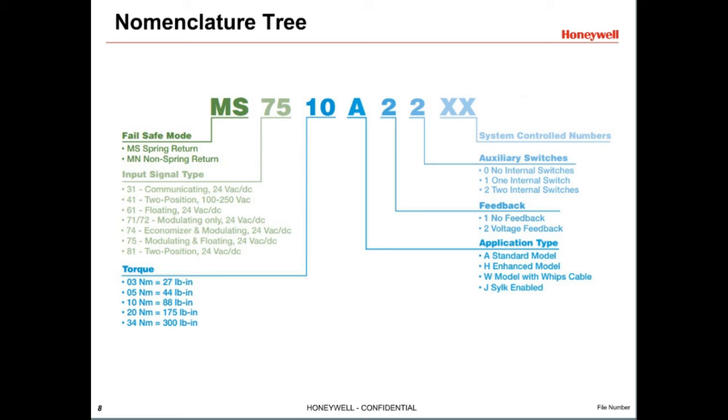For example, let's look at the MS7510A2206. The S indicates it is a spring return actuator; N would indicate a non-spring return fail-in-place actuator. The 75 means it can accept either a modulating or floating control signal. The 10 means it has 10 Newton meters, or 88 inch-pounds, of torque. Other control signal codes include 31 for communicating actuators, 41 for two-position line volt, and 61 for floating 24-volt. The letter A denotes a standard actuator; J would indicate a Sylk communicating actuator, which would also have 31 in the first part of the number.